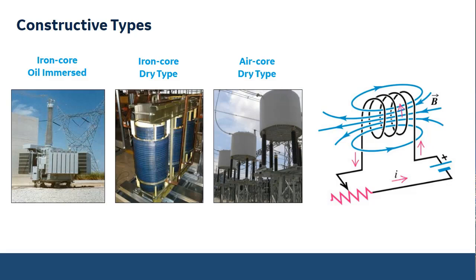So why use air core dry type and not the other two technologies? First, it depends on the application. The main characteristic of this technology is not having an iron core. And that means that an iron core can saturate when the reactor is exposed to very high current. For example, fault current limiting reactors. If the iron core reactor faces a fault current, let's say 20 or 30 kA, there is just an amount of magnetic field that the core can withstand. If it exceeds that, it saturates the core, and it basically changes the impedance of the reactor when the impedance is mostly needed during the fault to limit it.